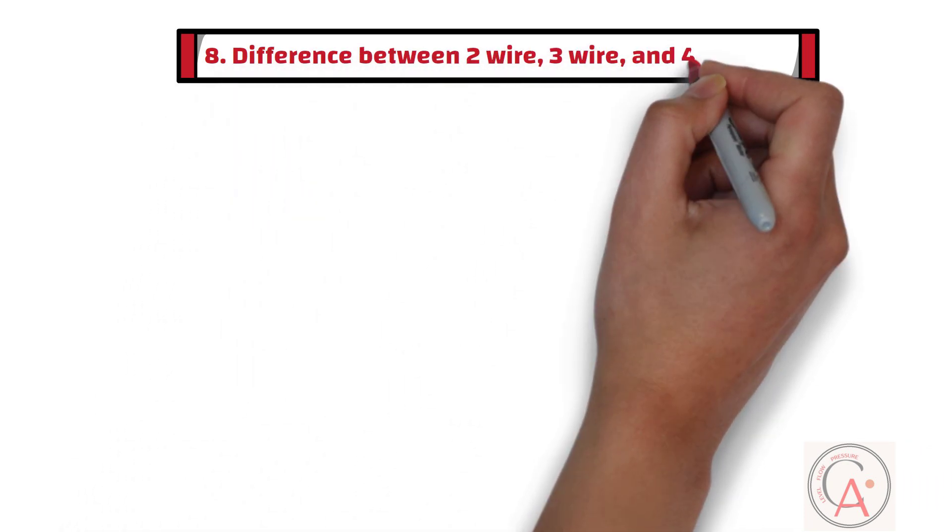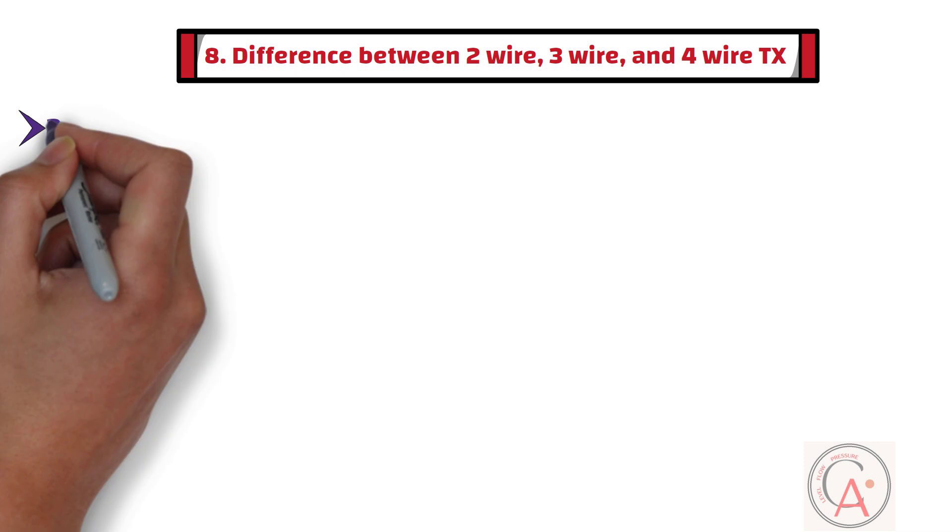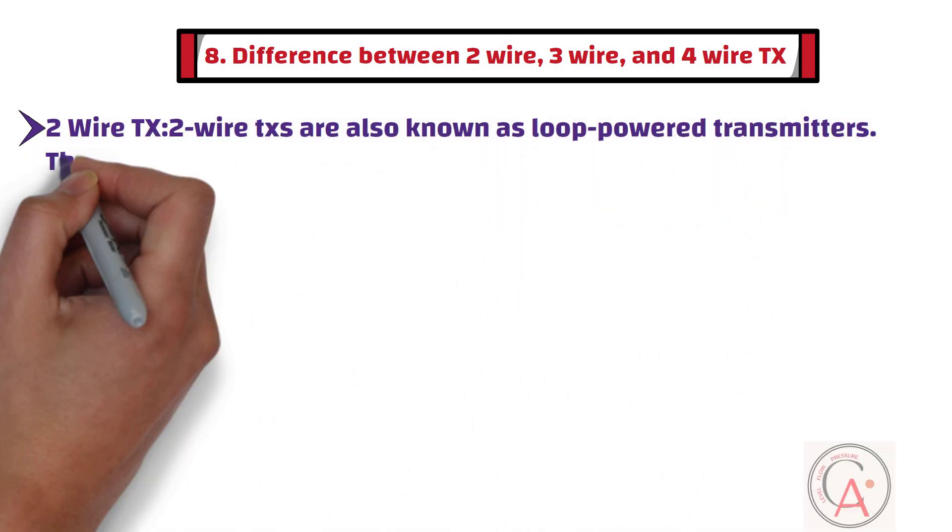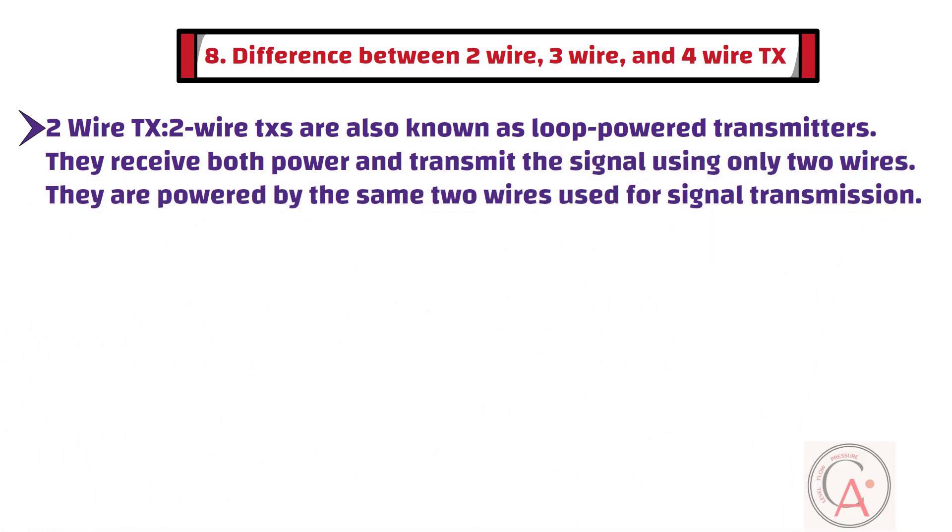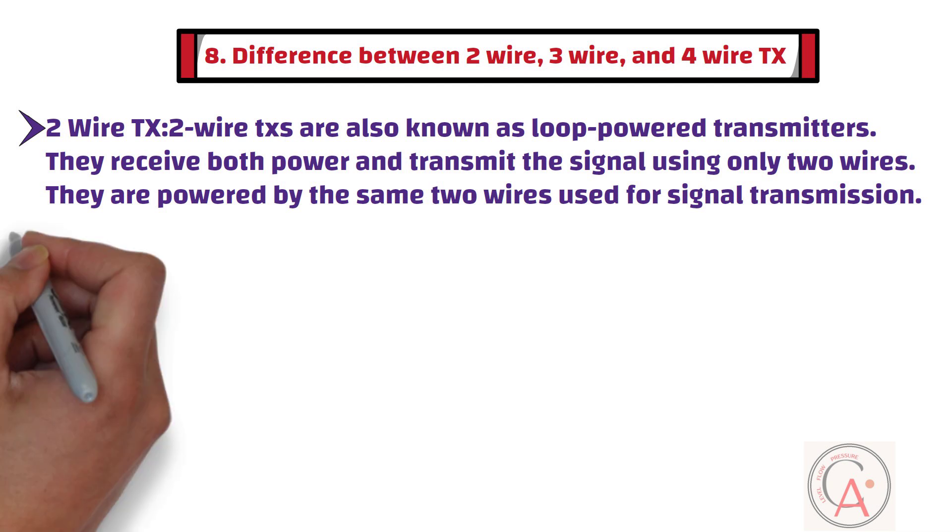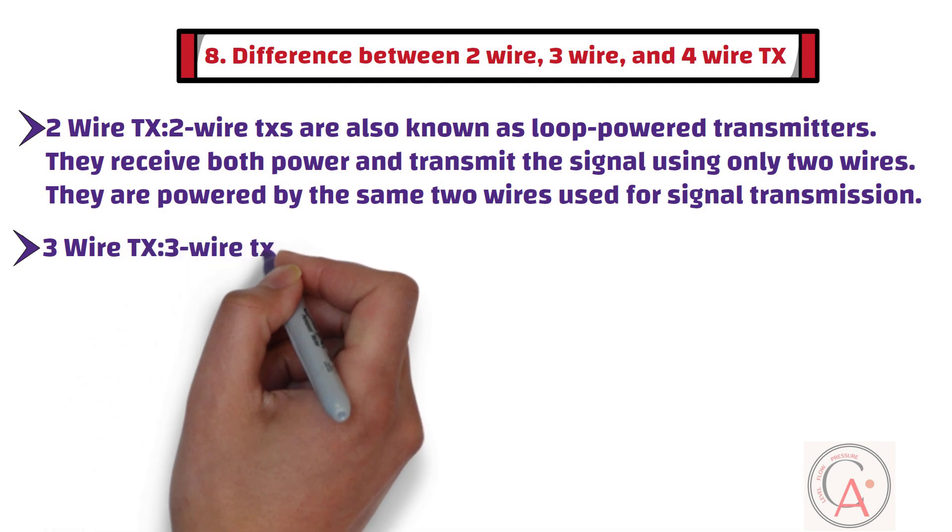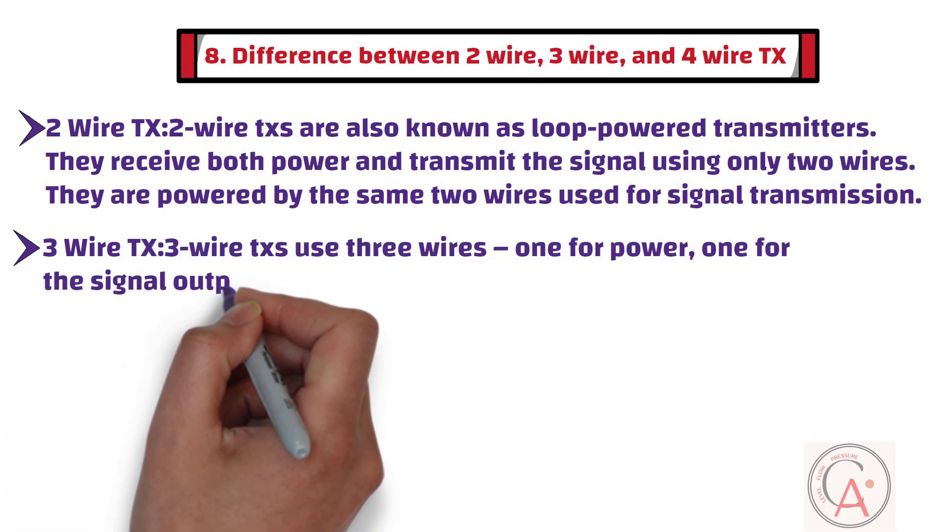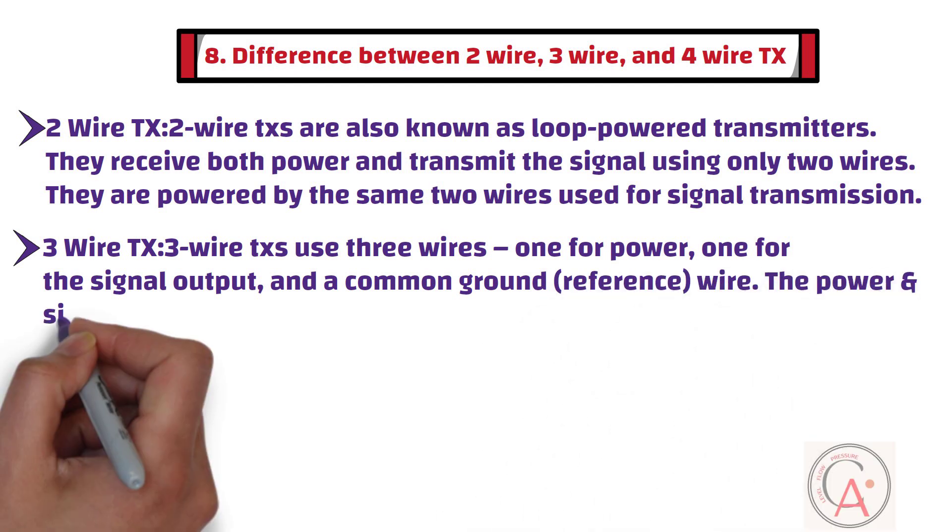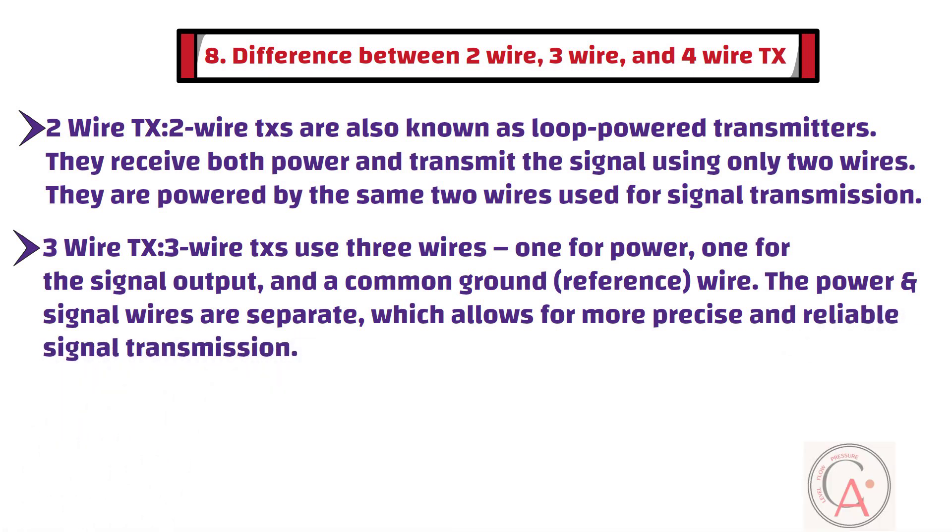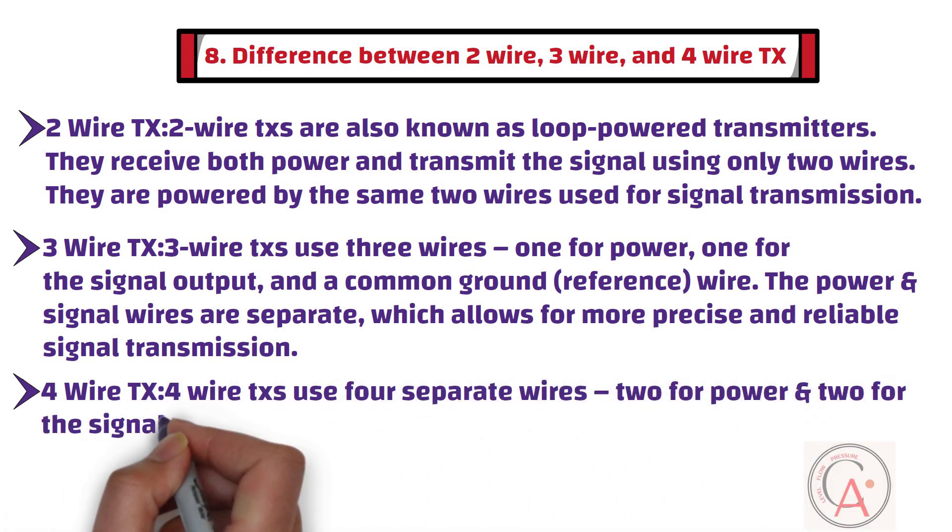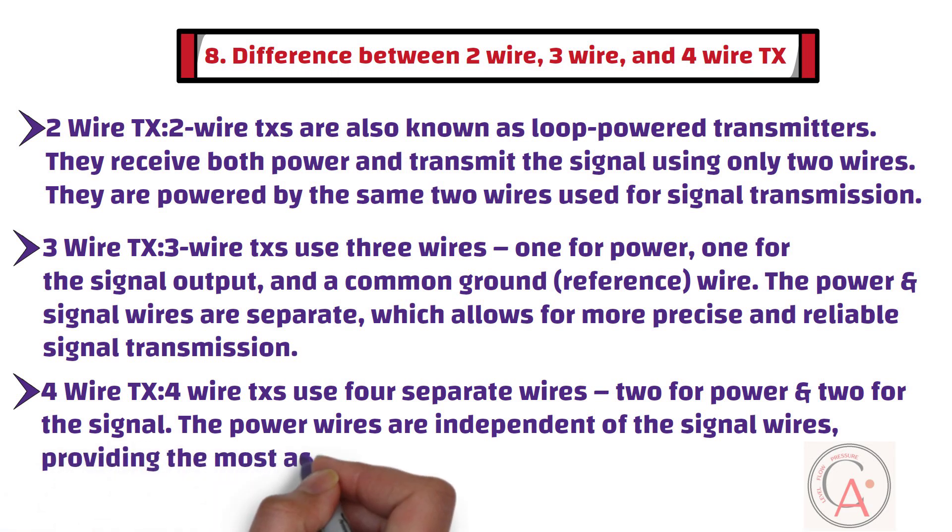The eighth question is, what is the difference between two-wire, three-wire, and four-wire transmitters? Two-wire transmitters are also known as loop-powered transmitters. They receive both power and transmit the signal using only two wires. Three-wire transmitters use three wires: one for power, one for the signal output, and a common ground or reference wire. The power and signal wires are separate, which allows for more precise and reliable signal transmission. Four-wire transmitters use four separate wires: two for power and two for the signal. The power wires are independent of the signal wires, providing the most accurate and reliable measurements.